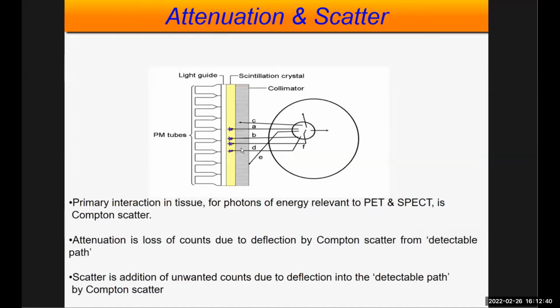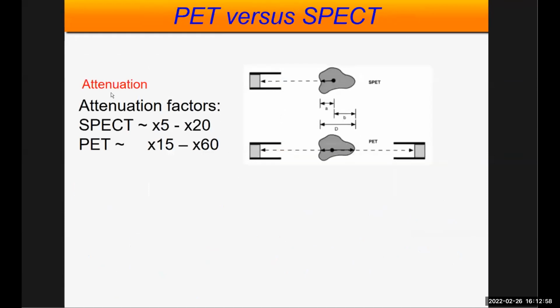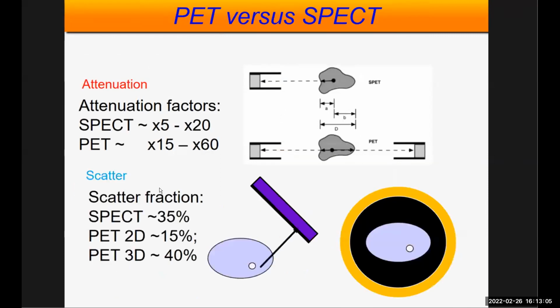Attenuation and scatter also affect your image quality. Primary attenuation is a loss of counts due to deflection by Compton scatter out of the detectable path. Scatter is the addition of unwanted counts due to deflection into the detectable path by Compton scattering. This is the attenuation factor in SPECT, which is 5 to 20 times, and in PET it is 15 to 60 times. The scatter fraction in SPECT is 35%, in PET 2D it is 15%, and in 3D it is 40%.